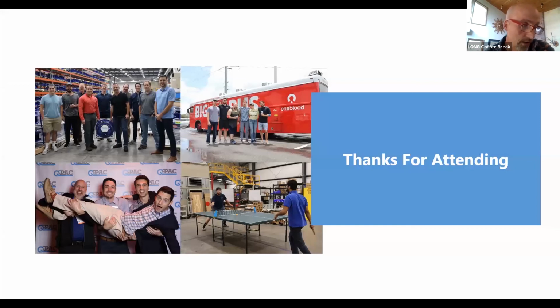There were 10 large air handlers on the project, over 155 total fans in fan arrays. In the base bid, every single fan had a dedicated VFD, so you can imagine the amount of electrical and controls wiring required for each individual VFD. We worked with Q-PAC to present the ECM fan array option to a relatively leery client that wanted to understand the technology.